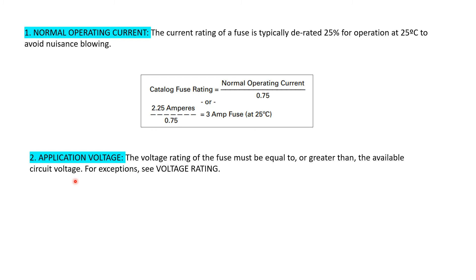Next is ambient temperature. The current carrying capacity of fuses is generally rated at 25 degrees centigrade, and they will give you that in the data sheet. If you ask for a 2 ampere fuse, they will give you a 2 ampere fuse, but the 2 ampere rating depends upon their testing condition. Basically their testing condition is 25 degrees C. But actually you are using your circuitry somewhere, depending upon your environment. It may be 40 degrees, 50 degrees, 60 degrees, or up to 85 degrees C.